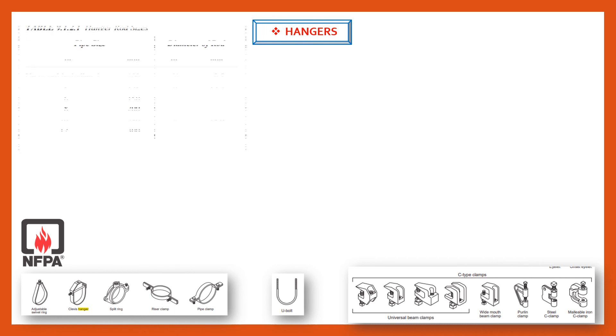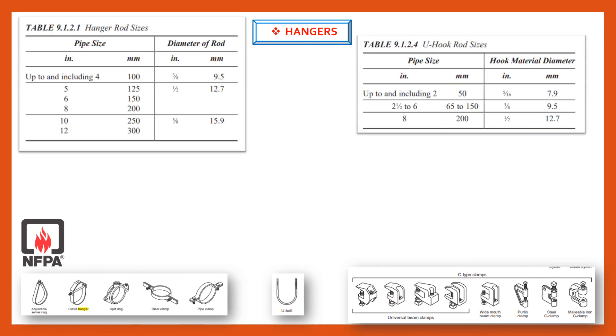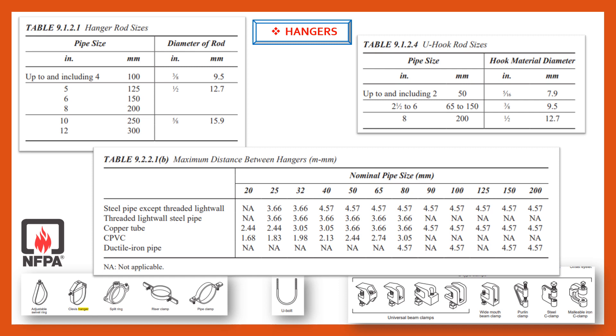In this slide, let's go through hanger rod sizes, U-hook rod sizes, and maximum distance between hanger to hanger as per NFPA 13. As we can see on screen, table 9.1.2.1 refers to hanger rod sizes. For example, if we are considering 10-inch to 12-inch pipe, then the hanger rod size shall be 15.9 mm. And let us have a look at maximum distance between hanger to hanger.